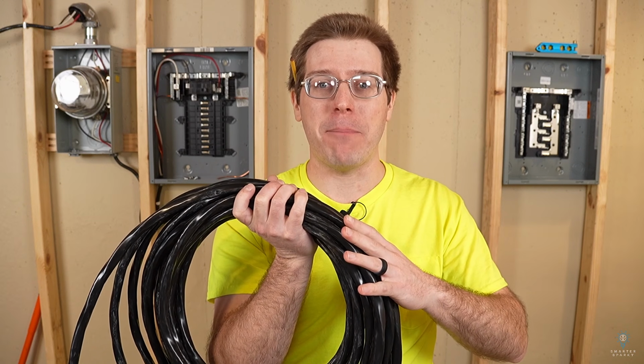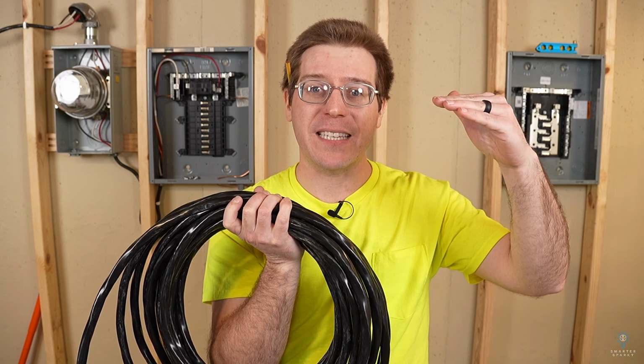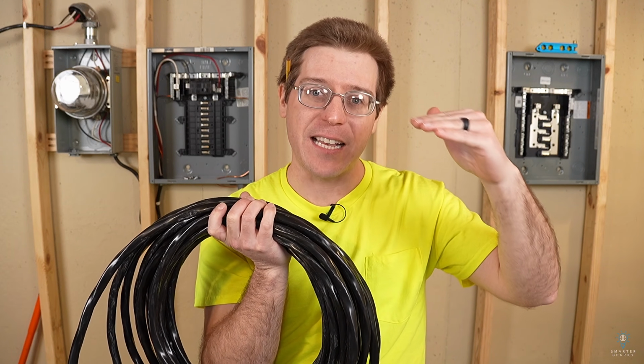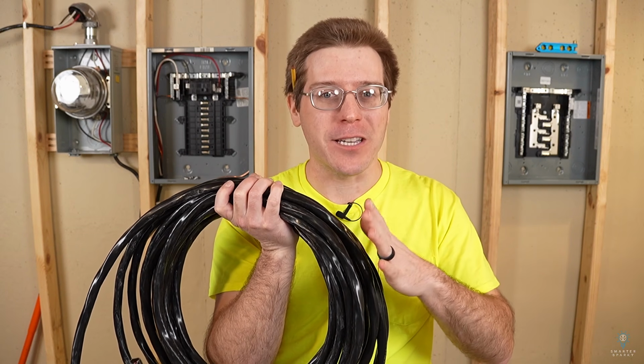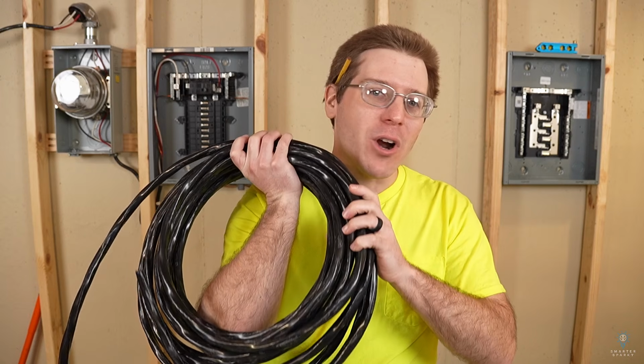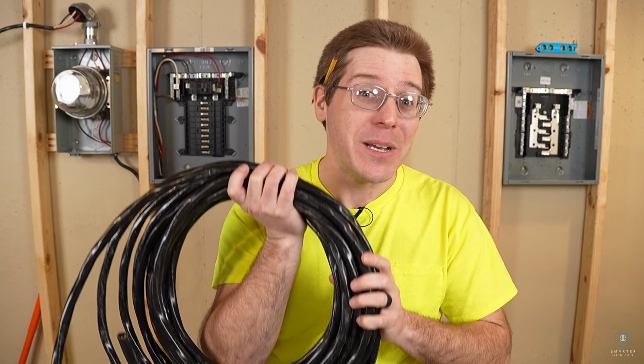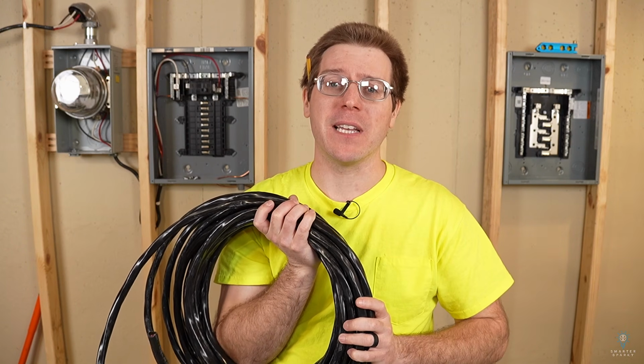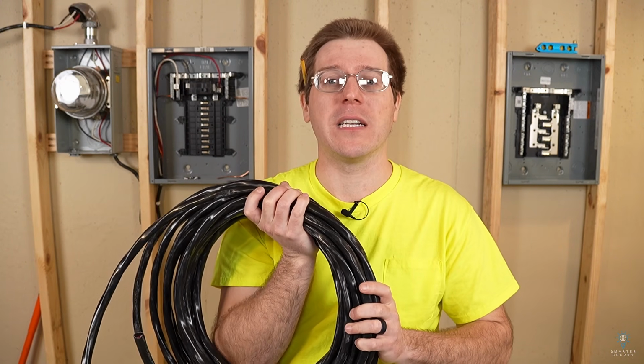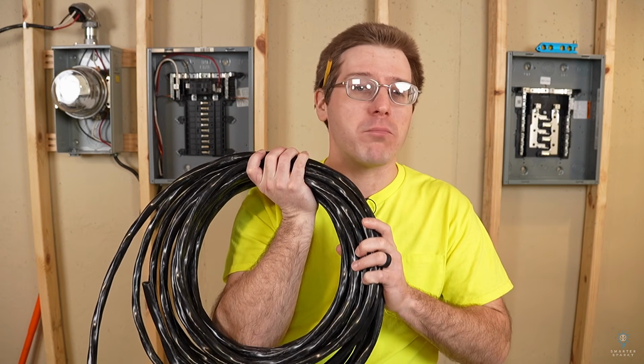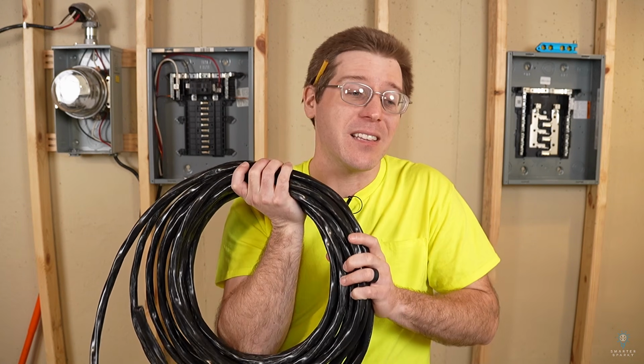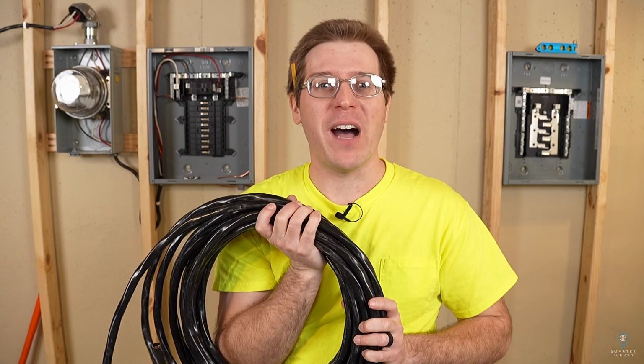So the code says when you have non-standard ampacity wire, you could actually protect it at the next standard size breaker. Again, so long as you promise that you're not actually gonna put 60 amps on this. There are no safeguards in place though that are going to ensure you never put 60 amps on this. And to be quite realistically honest, putting 60 amps on this probably isn't going to be a big deal. Again, the code says though, you can only put 55 amps on this.